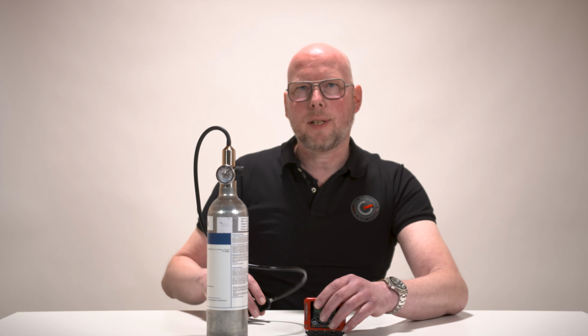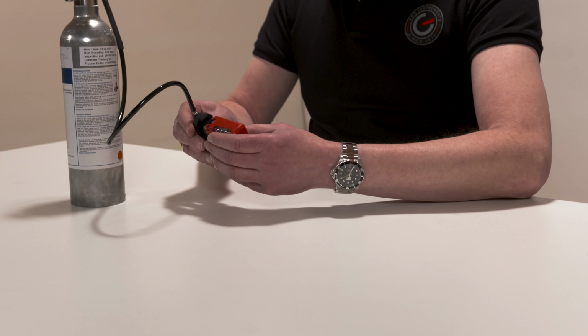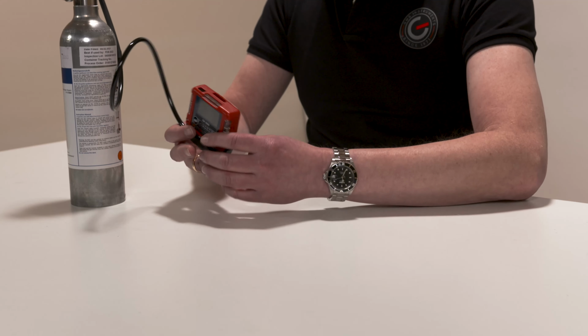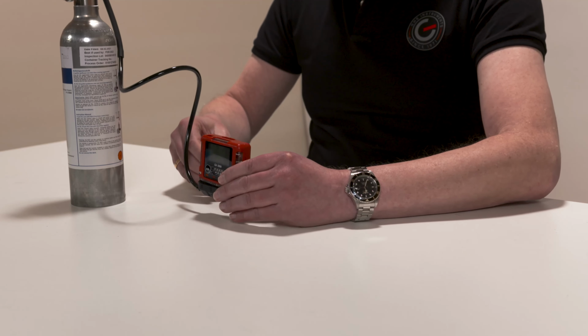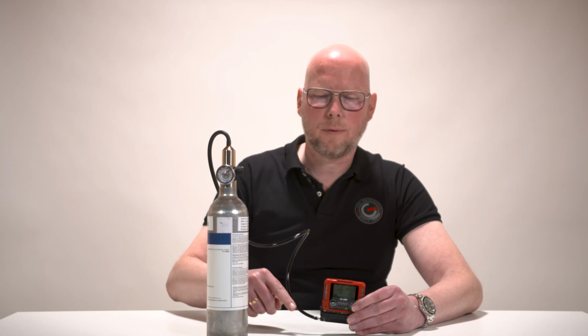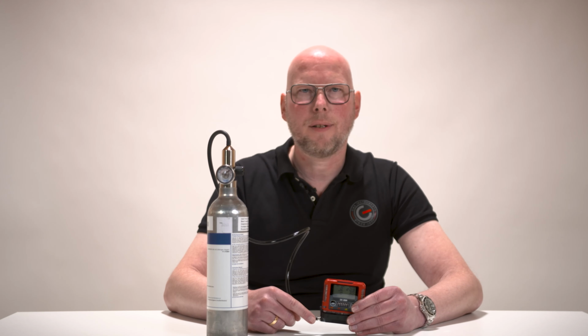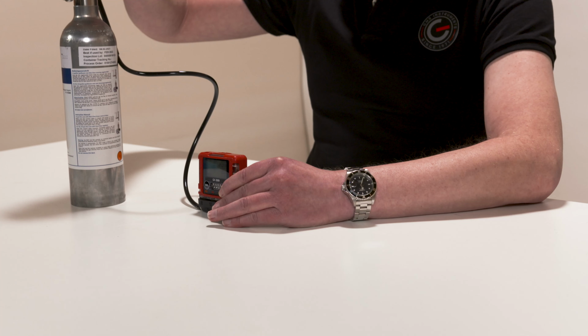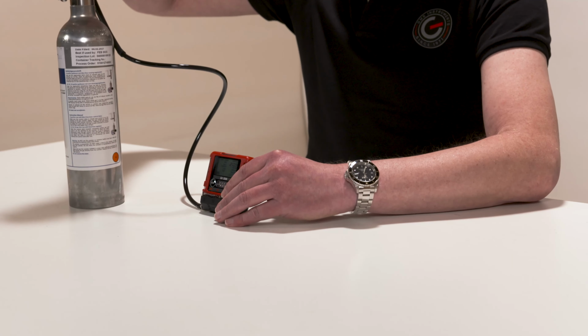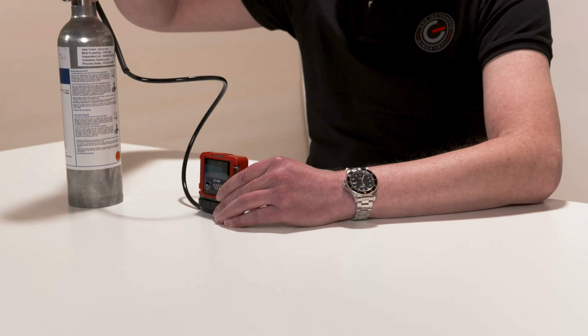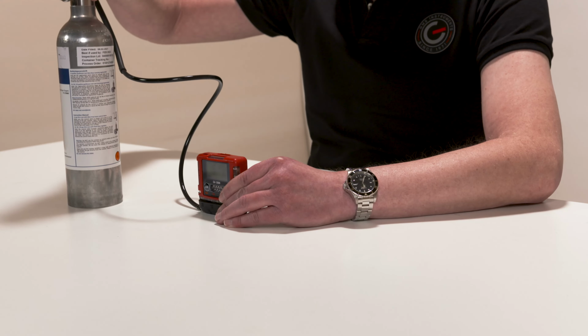Click the calibration adapter on the gas detector and connect the hose of the fixed flow regulator to the calibration adapter. Now open the fixed flow regulator so that the gases can flow from the cylinder to the gas detector.